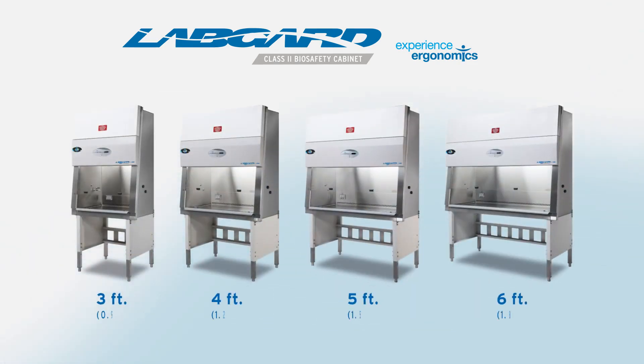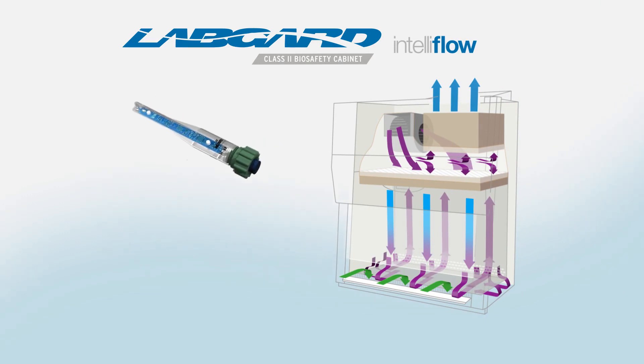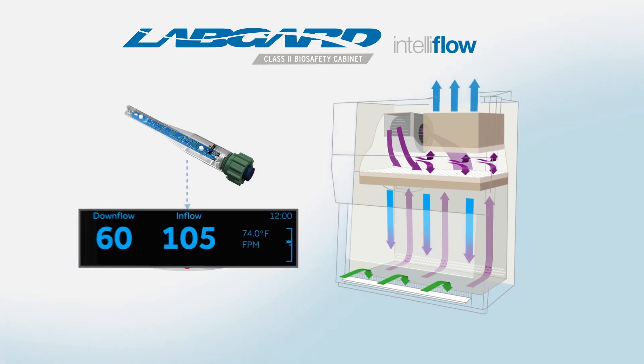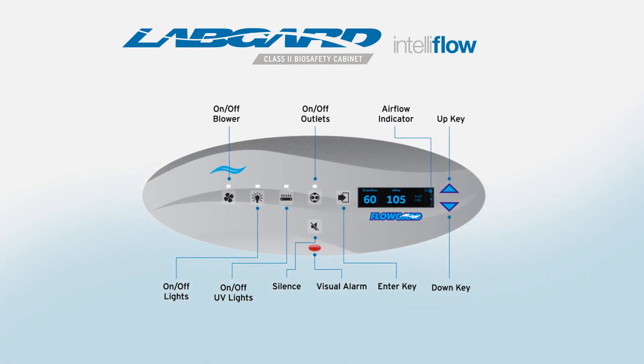Four sizes are available to match your workflow and laboratory size. Data from an airflow sensor that directly monitors exhaust airflow enables the FlowGard control panel to calculate and display cabinet performance data. Enhanced functions include timers, password protection, a filter life indicator, and a detailed service menu.